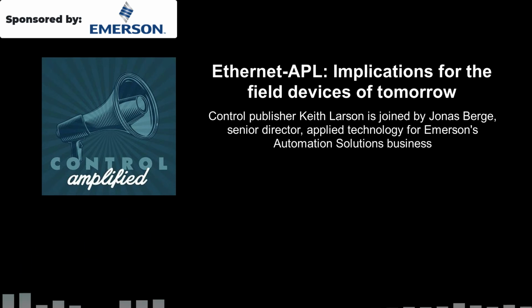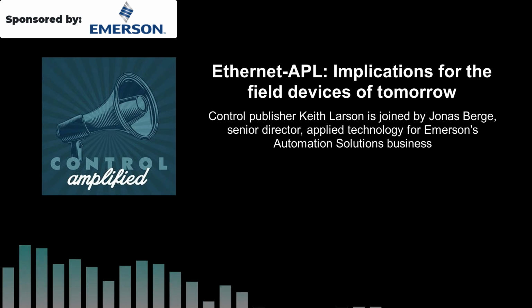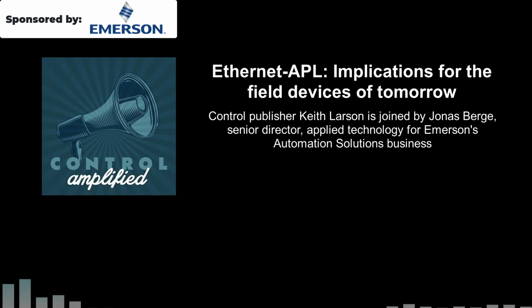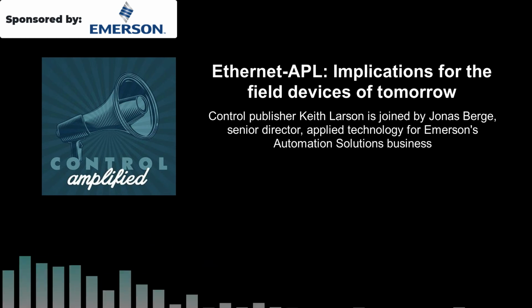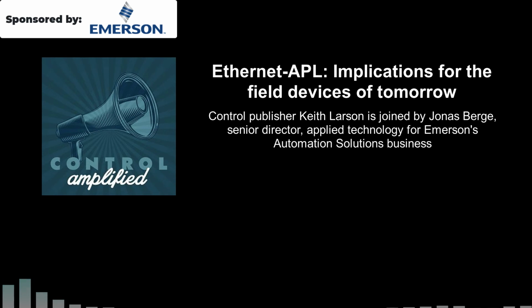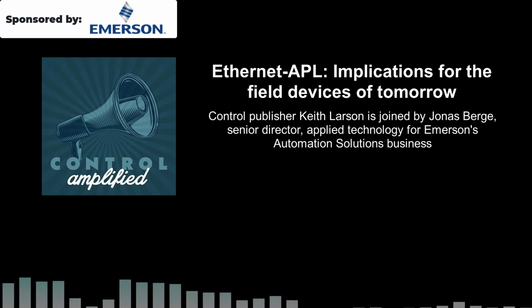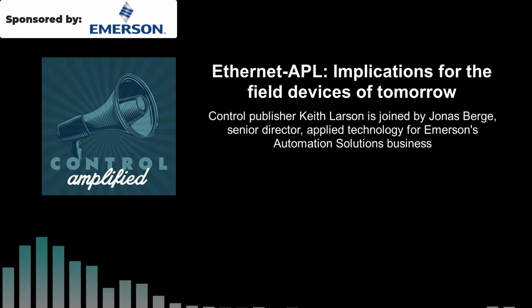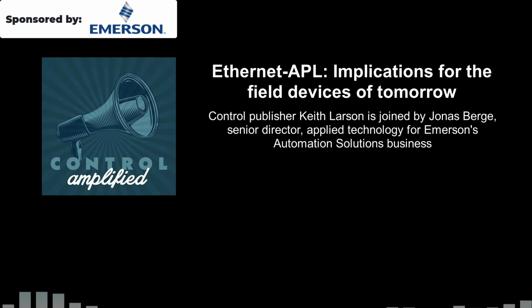Maybe on another note, faster sampling time also means faster control loops, which means better control. Faster response time also means approved APL devices could in the future be used for functional safety. With digital, we can avoid covert failures associated with analog signals. High speed enables safety instrumented functions, fire and gas, and machinery protection systems that are currently hardwired to go digital. So really all plant systems can go APL, not just the basic process control.